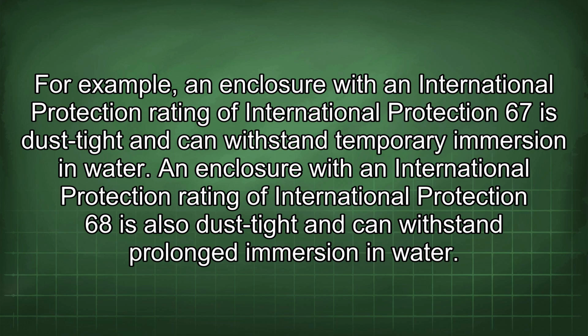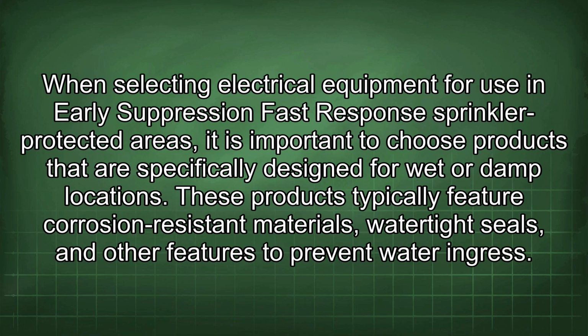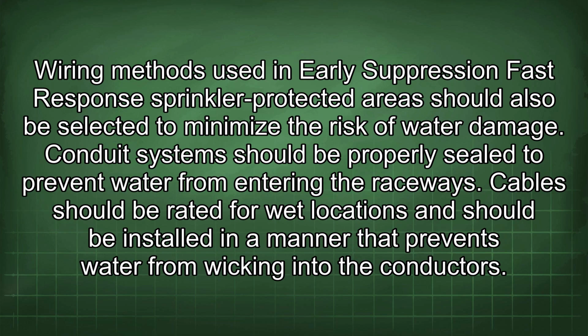When selecting electrical equipment for use in early suppression fast response sprinkler protected areas, it is important to choose products that are specifically designed for wet or damp locations. These products typically feature corrosion-resistant materials, watertight seals, and other features to prevent water ingress. Wiring methods used in early suppression fast response sprinkler protected areas should also be selected to minimize the risk of water damage.